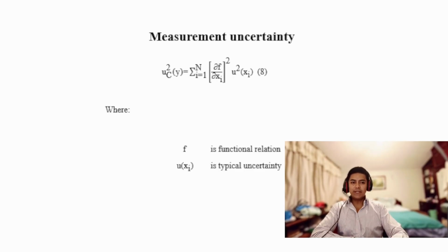The estimation of the typical combined uncertainty for the uniformity is obtained from the recommendations of JCGM, where their general form is equation 8. The points measured on the luminous surface are independent of each other. Therefore, they are considered uncorrelated.